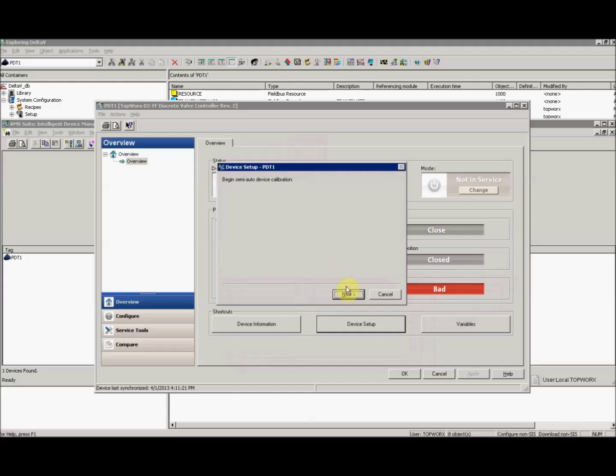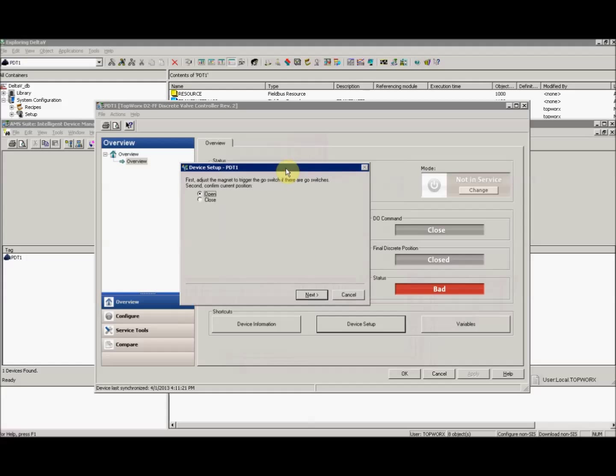It asks you if you want to begin the semi-auto device calibration. We'll select Next. Now it's saying adjust the target magnet for the go switches to its current position. Right now my device is closed, so I'll select Close and hit Next. It asks me, do I want to reverse the valve to the other position? I'll select Yes. And it should stroke it to the other limit. At this point, if your target magnet isn't over top of the open switch, adjust the target magnet. Once you've got it adjusted, in this case we'll select Open and we'll click Next.